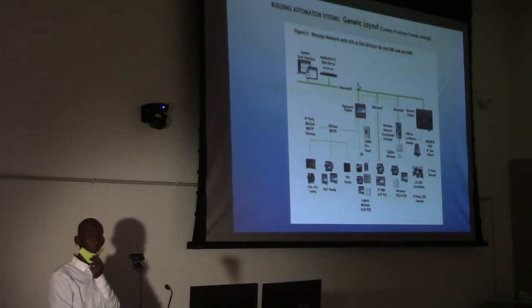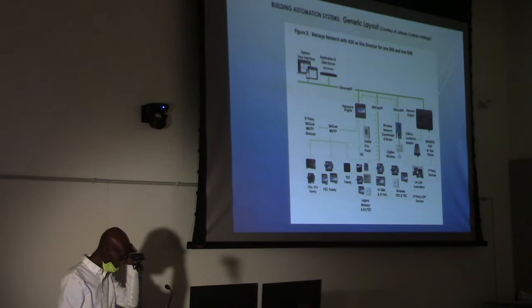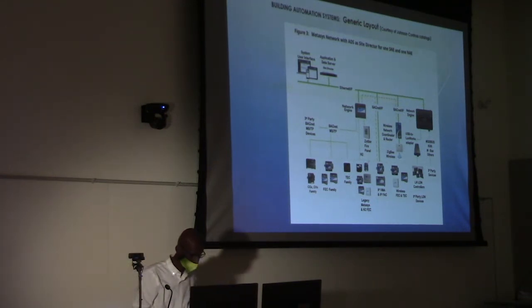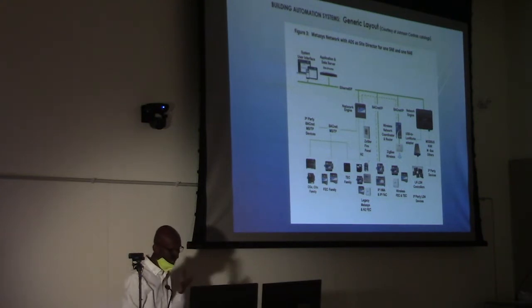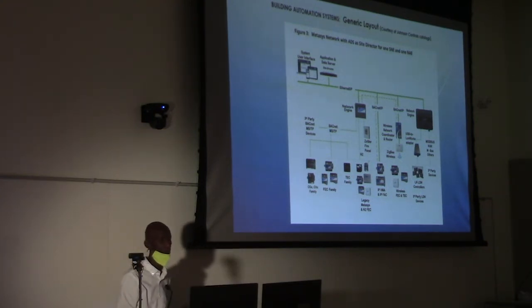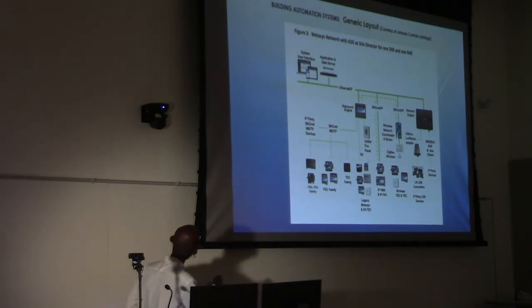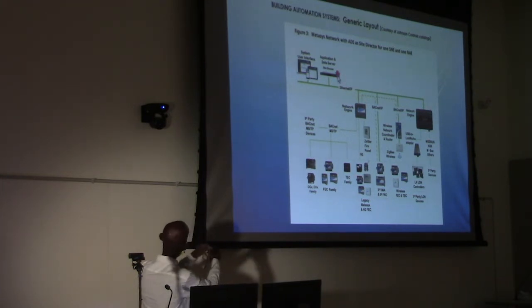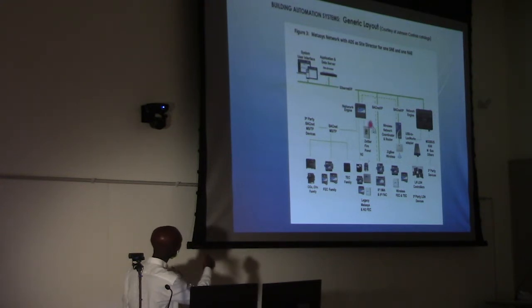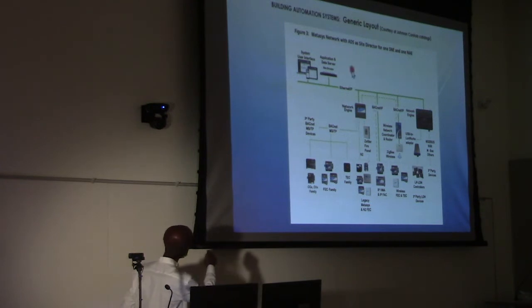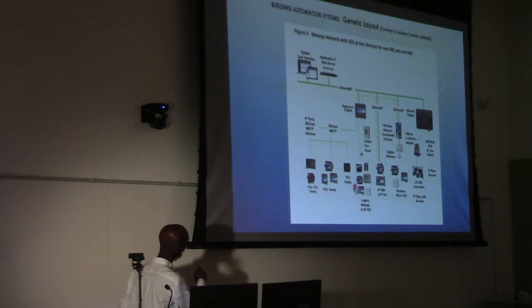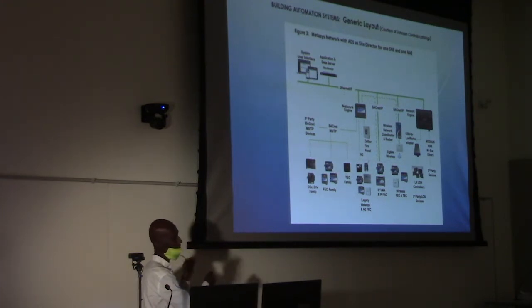Now, to make it a little bit sophisticated, this is a system we have at UMass. For instance, and this is just another Metasys network. I copied from Johnson Controls because we use Johnson Controls here. You can see we have user interface here. We have our server, and we communicate to our main controllers through Ethernet and IP addresses. And these main controllers communicate to field controllers through different BACnet, MSTP, which is master, slave, token passing. It's too hard. You won't have that in your quiz.